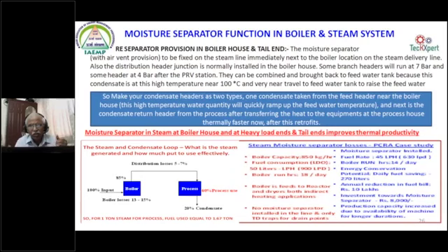A 60 degree temperature return is one aspect from the process, and a 100 degree plus return of condensate from the moisture separator at the boiler house is another type of return. Both the returns are combined together at the feed water tank. Automatically, for every 6 degrees rise in the feed water tank temperature, it goes to 1% fuel savings. That we can definitely achieve.